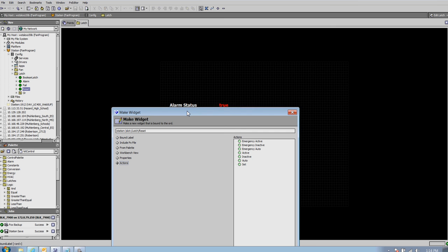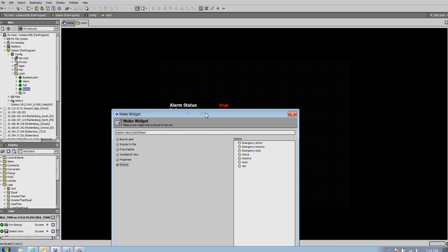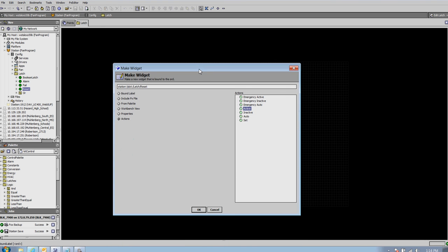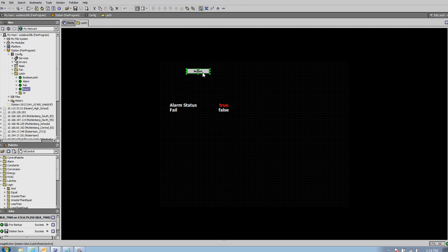Now what we want to do is reset that trigger or that clock input, which means that we need to get it to go to active state for a certain amount of time. Okay. We don't want to set it, because if we set it, then it won't be able to revert back to a default or a fallback. So we'll set it to active. We've already got our fallback set to false. This will make it true for a specified amount of time.